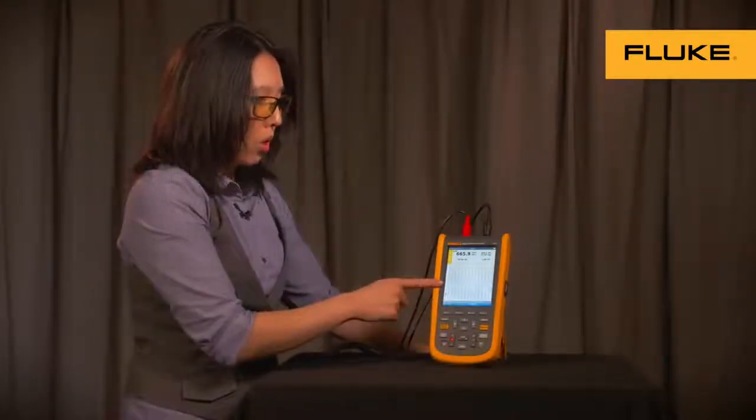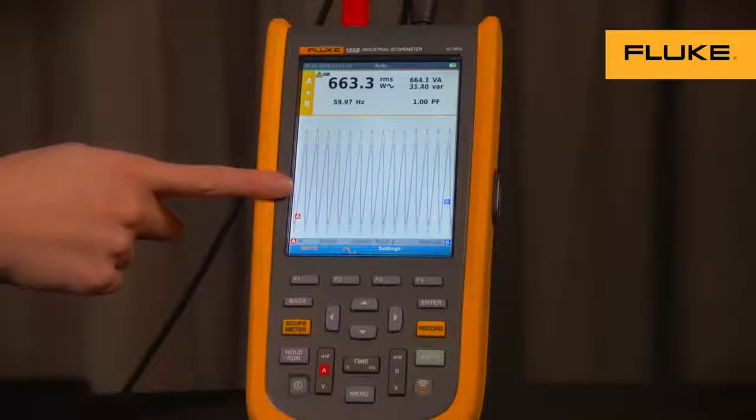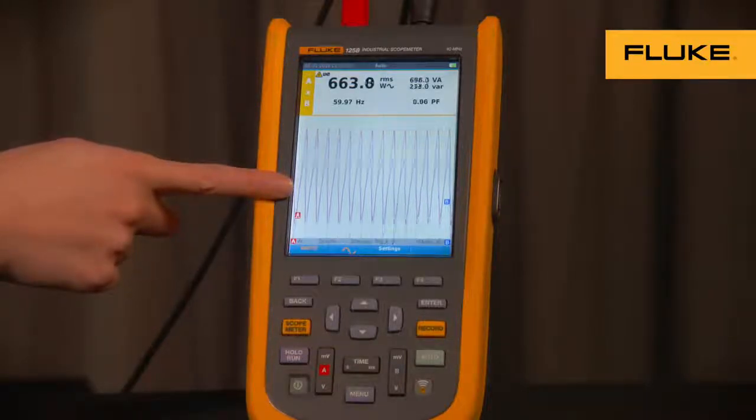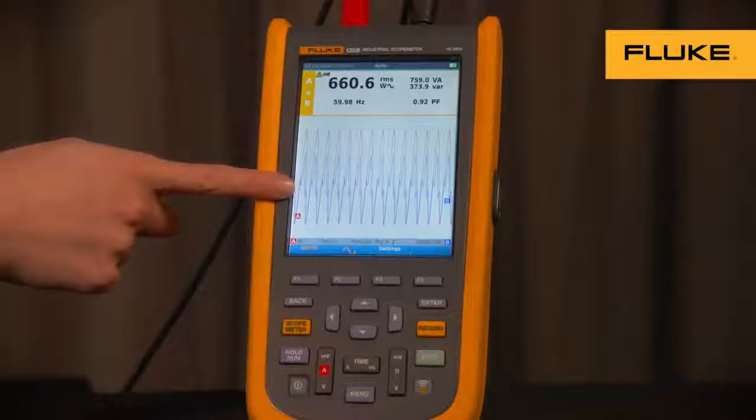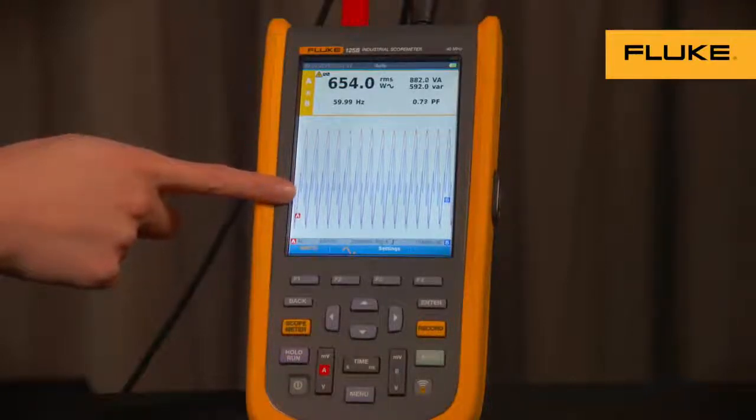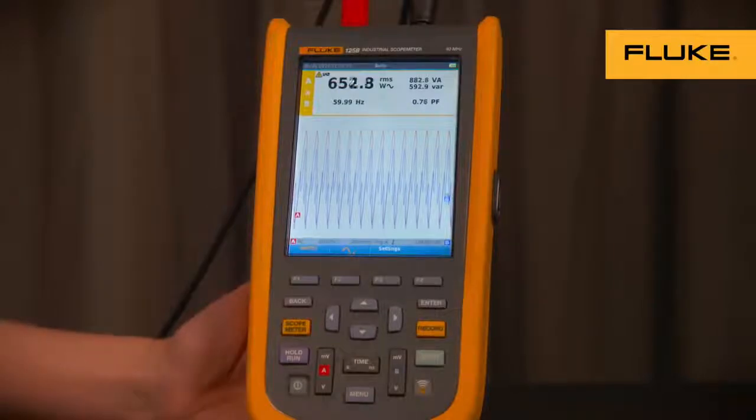If we add a third harmonic distortion on the current, notice the blue sine wave, which is our current measurement, experiences distortion. And at the same time, you can see your power factor and all your other power parameters change.